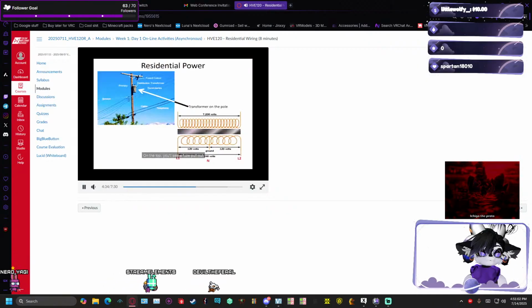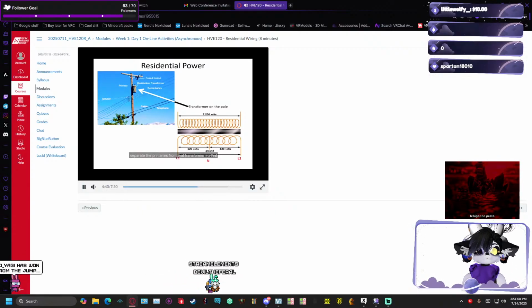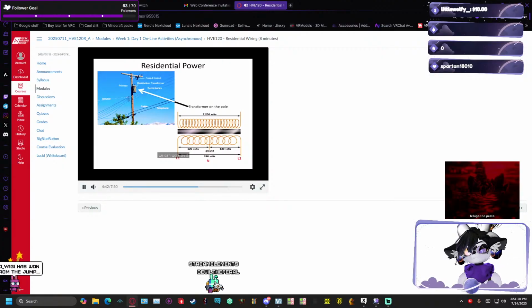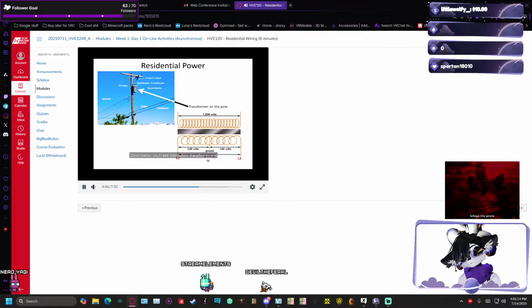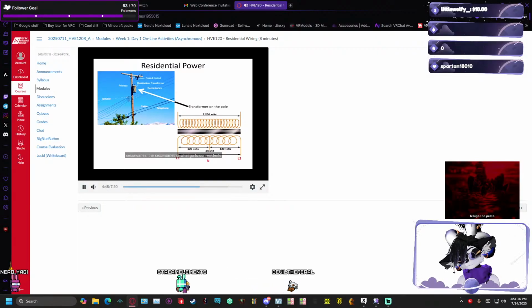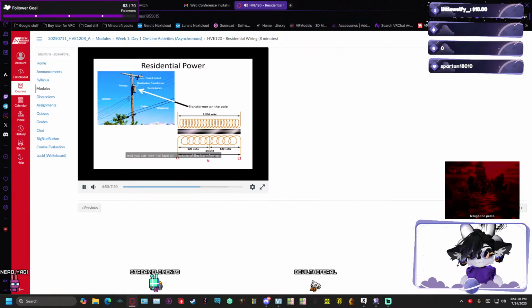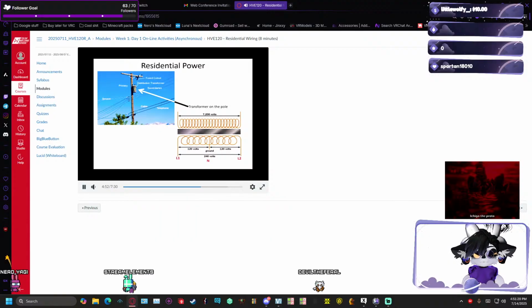On the top, you'll see a fuse pullout, which is where the lineman will use his hot stick and separate the primaries from that transformer so that we can work on it. Down below, you'll see distribution transformer and secondaries. The secondaries are what go to our residence, and you can see the taps on the side of the transformer.